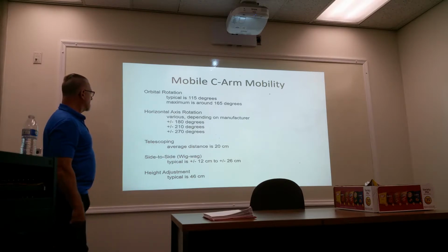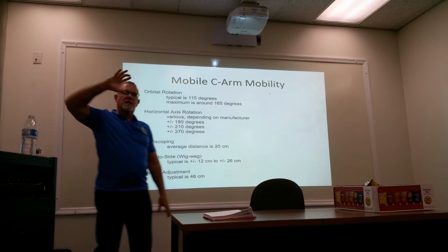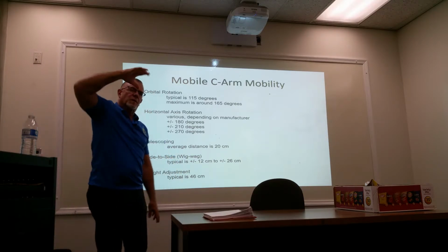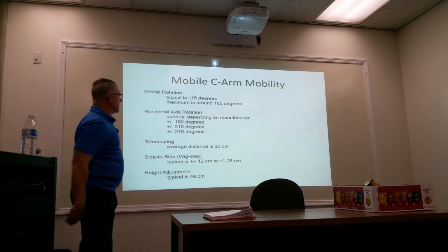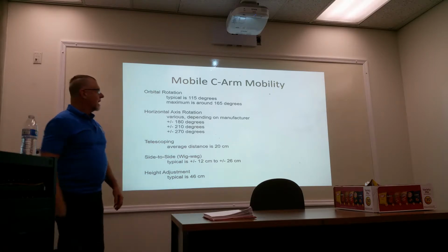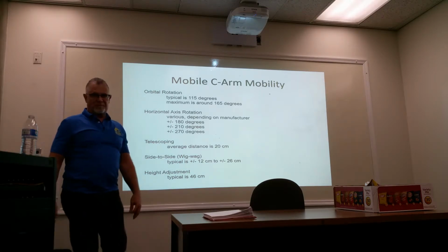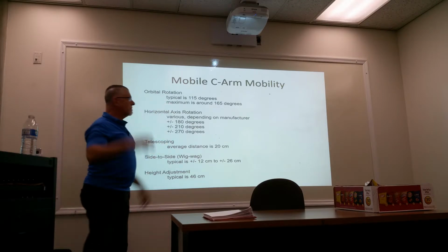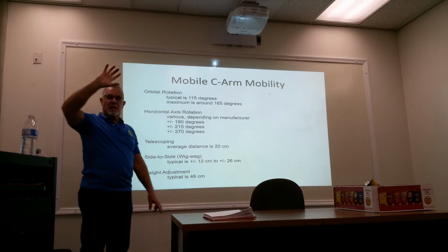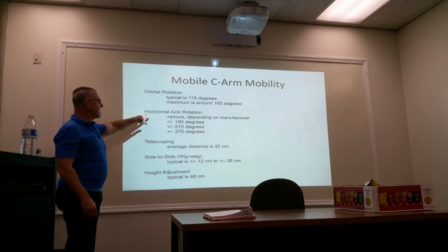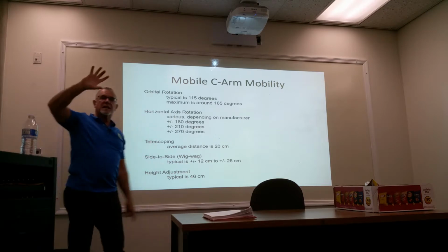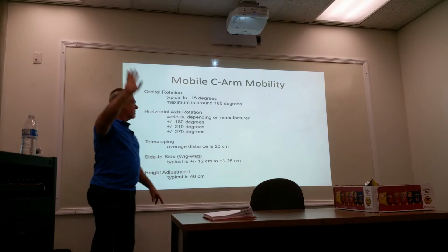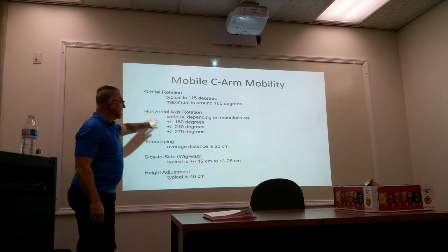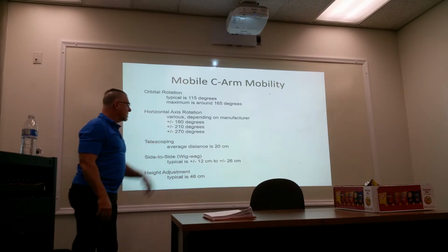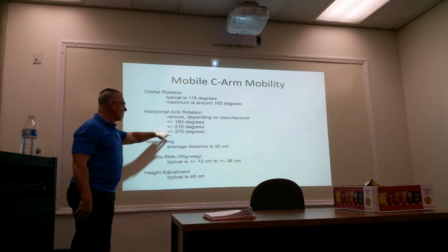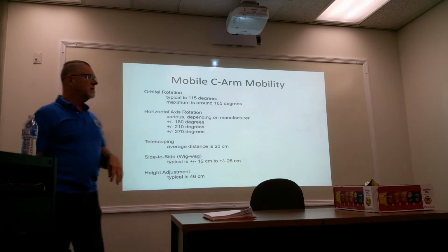And orbital rotation is where the C does this. That's orbital rotation. So you're talking AP to lateral? No. Notice typical is 115 degrees. For an AP or lateral, you need 180. So you're going to change the horizontal axis rotation. That's where the whole C does this. That's typically plus or minus 180 degrees. A lot of the newer units are plus or minus 210 or 270. Okay.